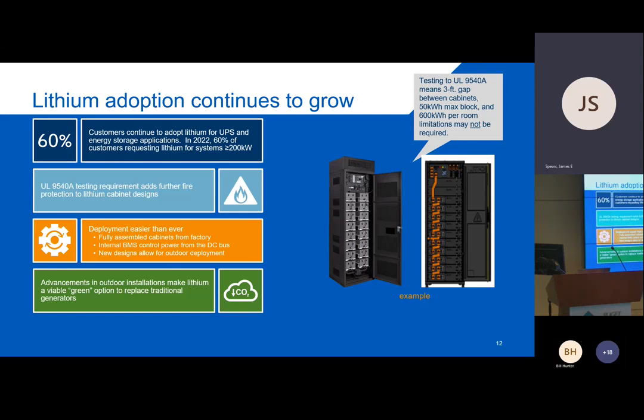Why did this happen? Well, if you look over on the left, down below, the successful UL 9540A testing was able to alleviate a lot of the safety concerns, not all of them, but a lot of them, both for the users and for the authorities having jurisdiction that are going to have to sign off on this installation and perhaps waive some of the more restrictive elements in the code that we'll get to eventually.